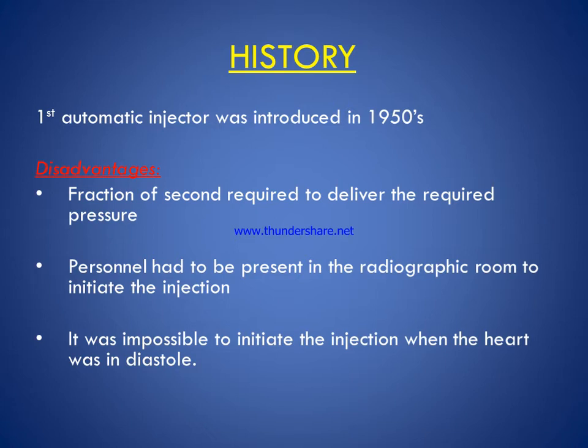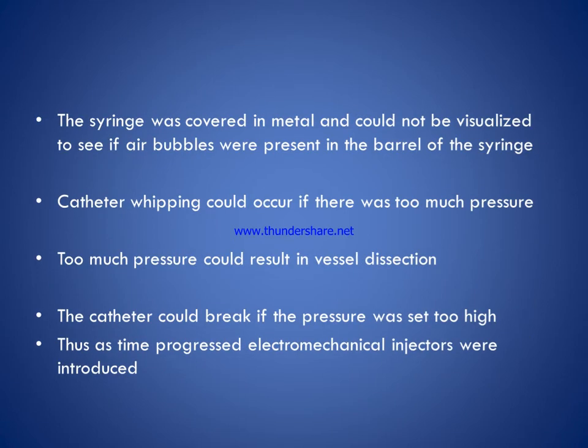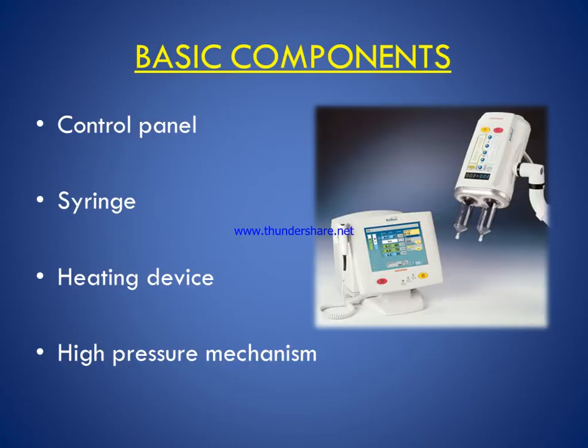Regarding the history of pressure injectors, the first automatic injector was introduced in 1950. Its disadvantages included: a fraction of a second was required to deliver the required pressures, personnel had to be present in the radiographic room to initiate the injection, it was impossible to initiate the injection when the heart was in diastole, the syringe was covered in metal and could not be visualized to check for air bubbles, catheter whipping could occur if there was too much pressure, too much pressure could result in vascular dissection, and the catheter could break if pressure was too high. Thus, over time, electromechanical injectors were introduced.